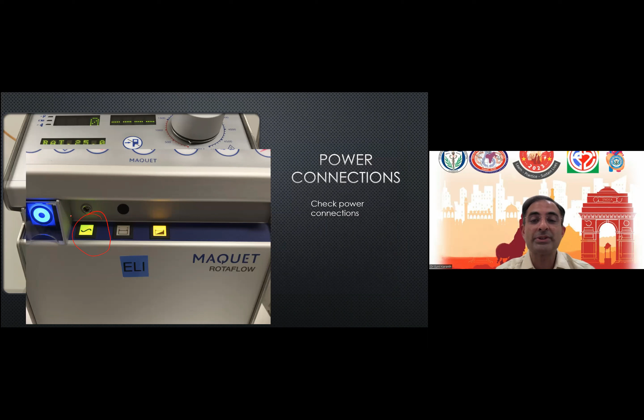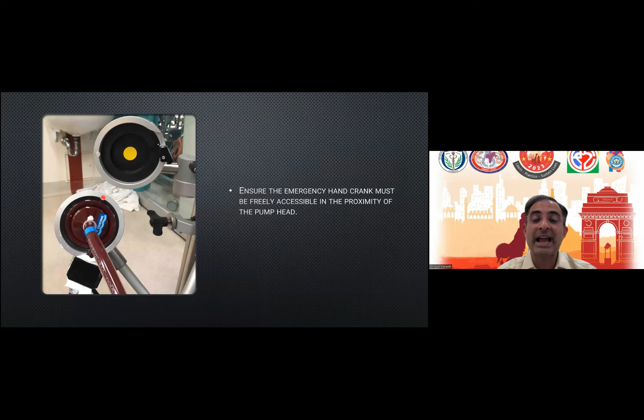So it is very important to ensure that the AC power connections are switched on. And as a safety mechanism, ensure that the hand crank is loaded and fixed by its clamp very close to the ECMO pump, so it is accessible and in close proximity to the pump head.